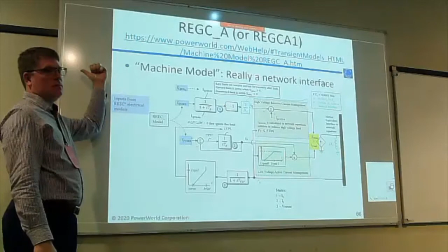Yeah. So to fix this problem, again, we have this thing that says high voltage reactive current management. Again, what it should really say is software fix so that we don't have these big voltage spikes. And so what it says is if the voltage goes above some threshold, it's going to suck extra vars out for a few time steps just to pull the voltage down to clip it to some value.